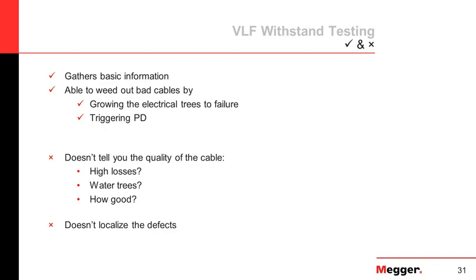A question from the audience: they've encountered a situation where the cable failed 24 hours after passing a VLF withstand test. What would cause that? Yeah, a lot of times people cheat their test time — instead of doing an hour test they'll do a 10 or 15-minute test. Statistically you get a good majority within 15 minutes, but a lot of times they'll partially grow something, put it in service, and it grows the rest of the way and fails. That happens quite often because people don't apply the right voltage or don't test long enough.